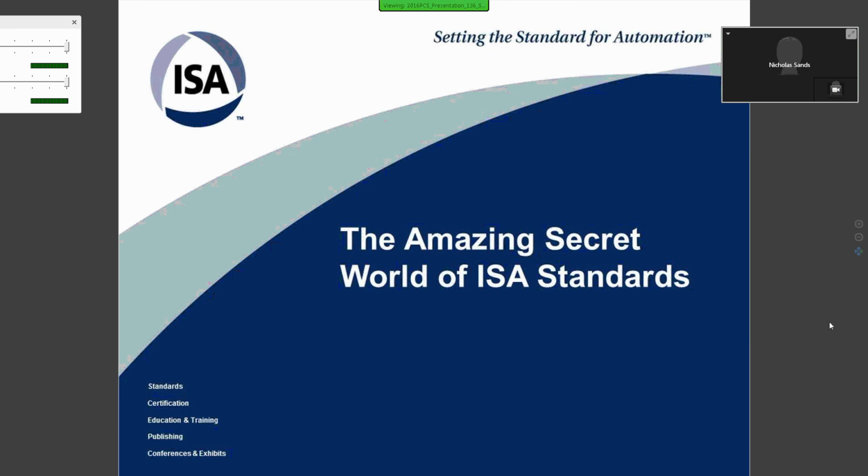Well, let me just mention, this is Greg McMillan. We actually use the ISA technical report and standard on valve response for our project, and it turns out that as we worked through this, we found out that it was for a steam system where we had 31 feed forwards and 3 overrides and a whole bunch of let-down pressure controllers with a lot of tight control requirements, and it turns out that the valve dynamics largely determined the performance and the tuning, and also the dynamic compensation for the feed forward.